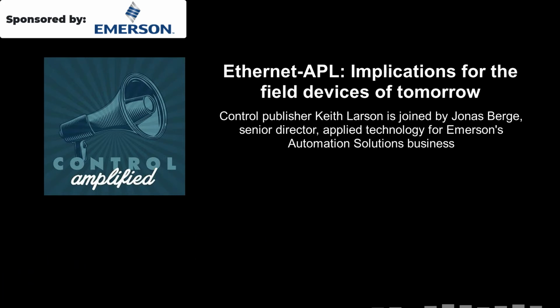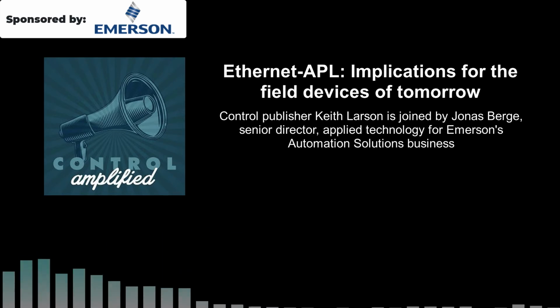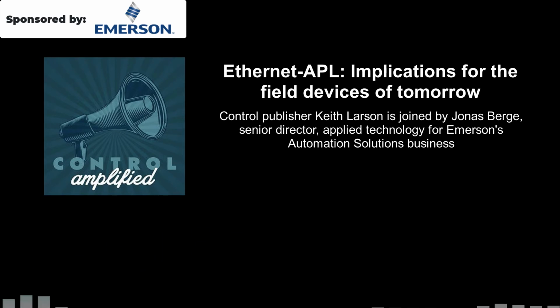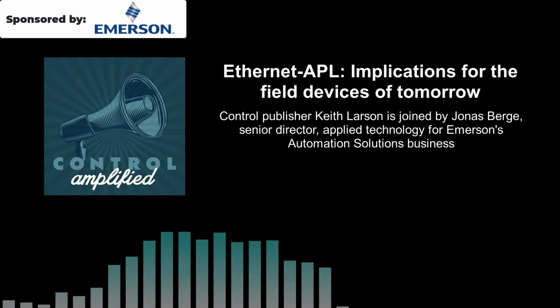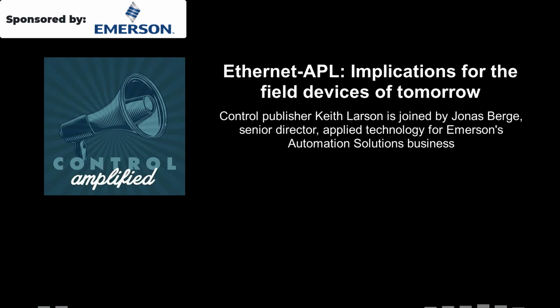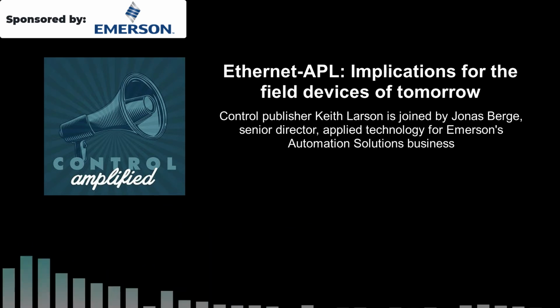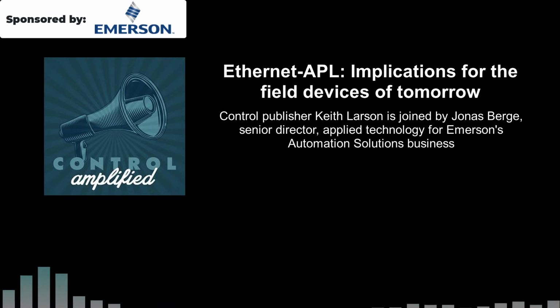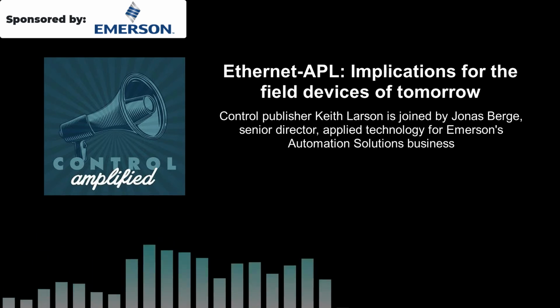Absolutely. For a radar level transmitter, more power means it can use frequency modulated continuous wave, or FMCW, sensing technology instead of the simpler pulsed radar. FMCW has greater temperature stability and is better at handling disturbing echoes, particularly in tall tanks. It does require advanced signal processing, but with the power from APL, transmitters will be able to provide faster update rates than in the past.